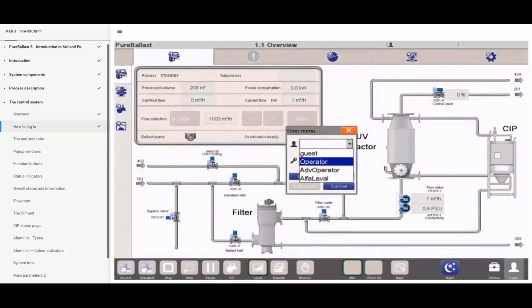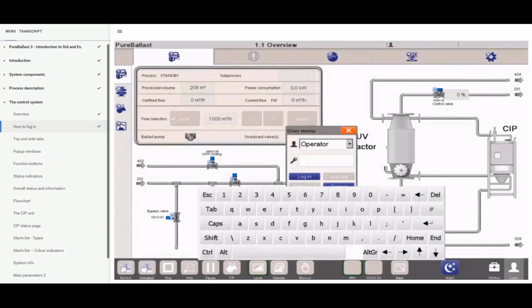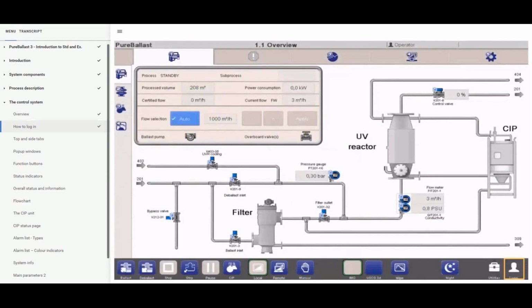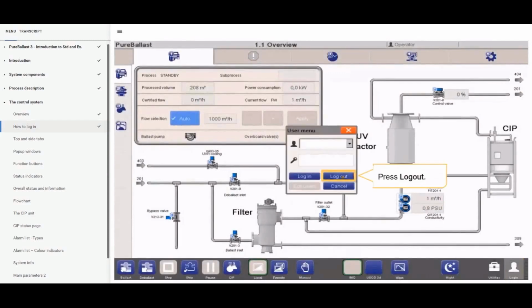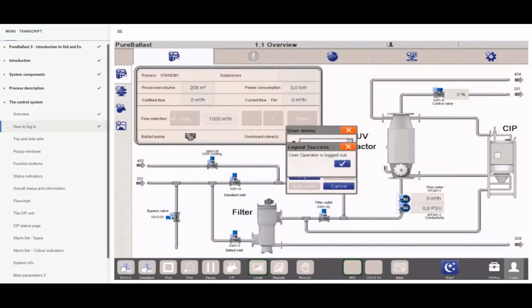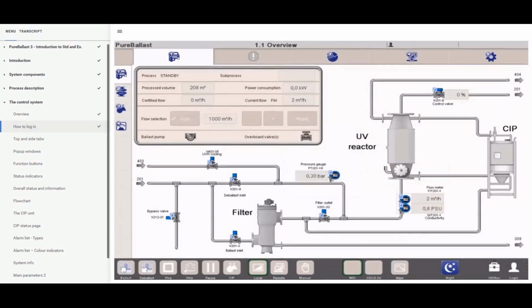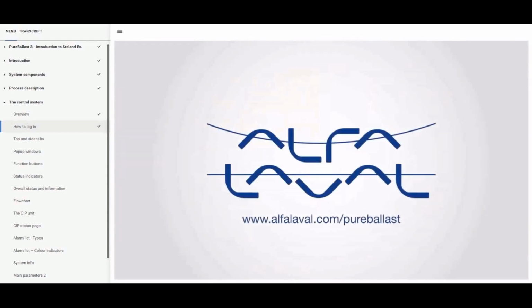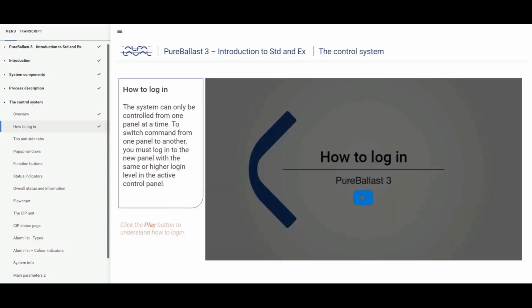Choose Login Level and select it. Enter password and press Login or Enter. The passwords for Operator and Advanced Operator can be found in the system manual. To log out, press the Login button and then press Log Out. Make sure to log out after the Advanced Operator or Alfa Laval level has been used, to avoid changing any parameters by accident and risk of running a non-compliant operation. Click Next to continue.